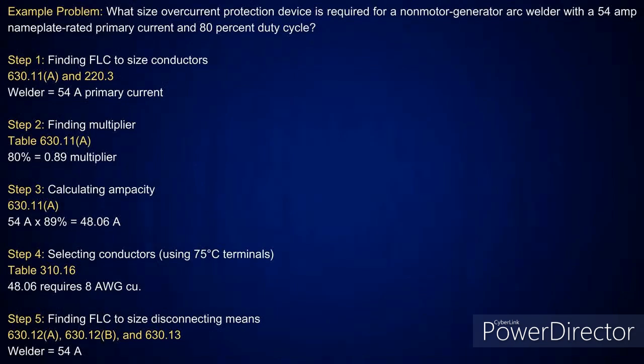Okay? Right. Now, this is where we get into welders. You're going to go over and look at 630.11A. When I start looking at this particular chapter, there are three types you're going to look at: your resistance type welders, and then your non-motor generator welders and generator type welders. When you look at 630.11A, it ties you in with Table 630.11A, and that's where you get your duty cycle multiplication factors for the arc welder.